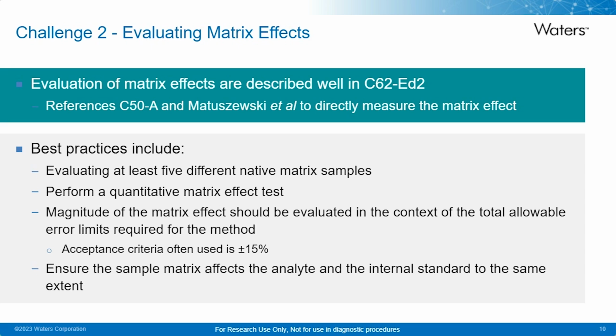The matrix effect evaluation is described really well in the CLSI C62A edition 2 guidelines, which references a great paper by Matuszewski et al. It describes the best practices of evaluating at least 5 different native matrix samples to perform a quantitative test to evaluate matrix effects with total allowable error limits, and also ensure that the sample matrix affects the analyte and internal standard to the same extent.